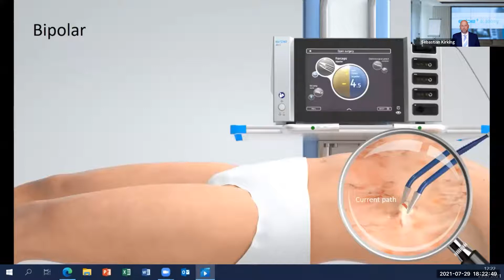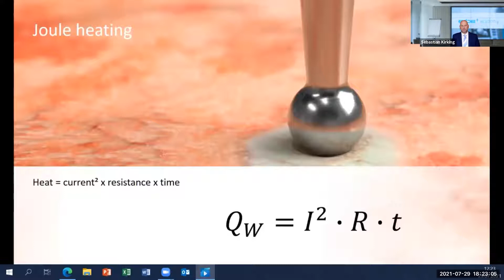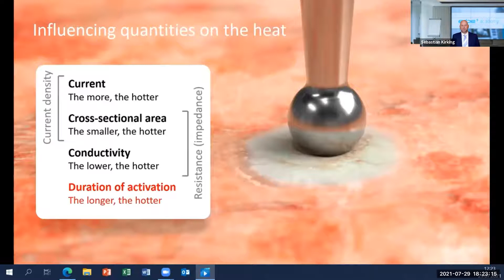Now, what are the influencing factors on the temperature and on the resulting tissue effect? As the law of Joule heating shows, the temperature depends on the intensity of the electric current, the resistance, and how long the instrument is activated. To make it less mathematical, the more current is used, the smaller the diameter, the lower the conductivity of the tissue, and the longer the instrument is activated, the hotter the tissue becomes.